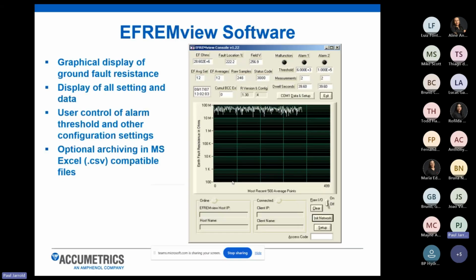This is the EFREMview software to give you an example of what that looks like. Basically, this is very normal. You can see the scattering of this resistance measurement that we're taking. This would be very normal on a customer's machine. We're taking a measurement, in this example, about every 40 seconds. In every 40 seconds, that value of resistance does change slightly, and it's going to range from 10 megohms up to 100 megohms in this case. That's very normal and what we would expect to see.